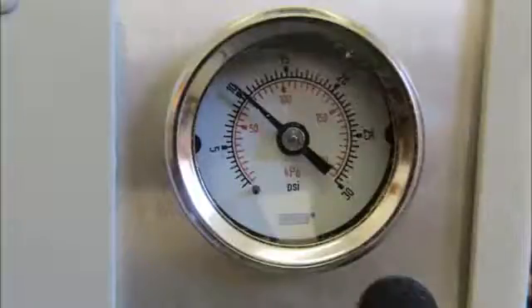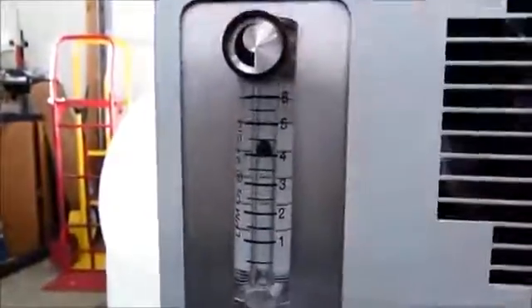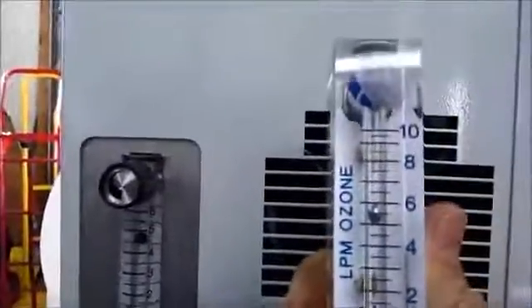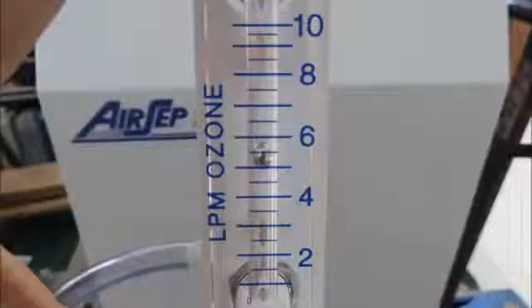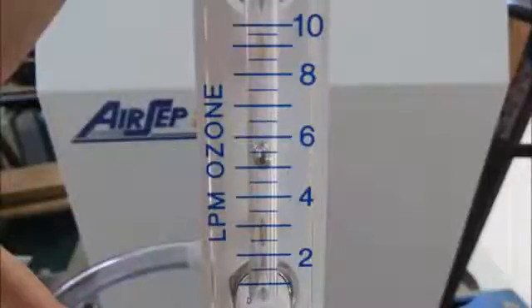Then we'll go to the left-hand side of the unit and look at the flow gauge with the flow adjustment. Turning it clockwise shuts down the flow, and turning it counterclockwise opens it back up. We want to set it to about 5.5 liters per minute as measured on our flow gauge. Here's a close-up showing the measurement at 5.5 liters per minute. Then it should be steady coming out of your oxygen concentrator.